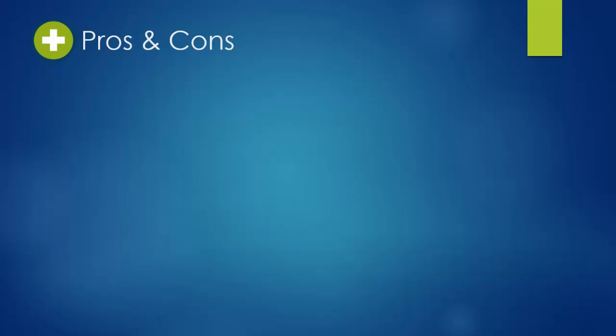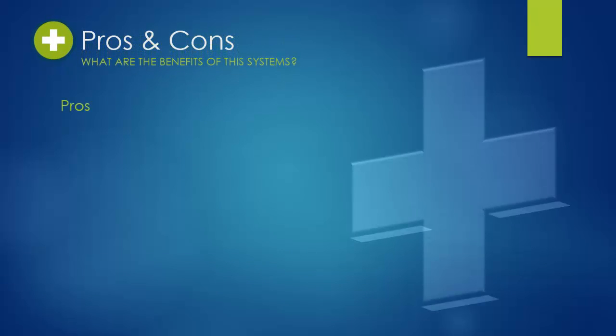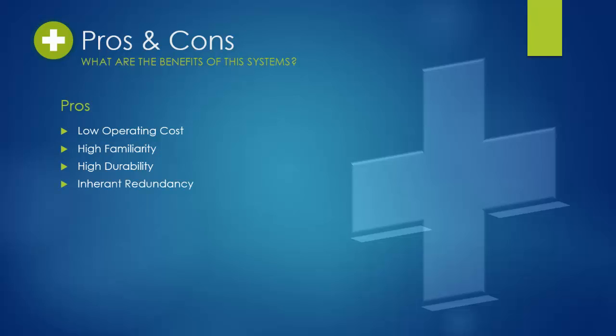After defining the system components, we can now discuss the pros and cons of the ground source heat pump system we have outlined. The advantages of the ground source heat pump system include low operating cost due to the ability to share loads between spaces and transfer heat to and from the ground. High familiarity due to the frequent use of heat pumps. High durability due to the life and predicted maintenance for the heat pumps. Also, the bores have a life of 50 years and will not need maintenance. Redundancy due to the large number of boreholes. Adaptability due to the ease of installing and moving heat pumps.